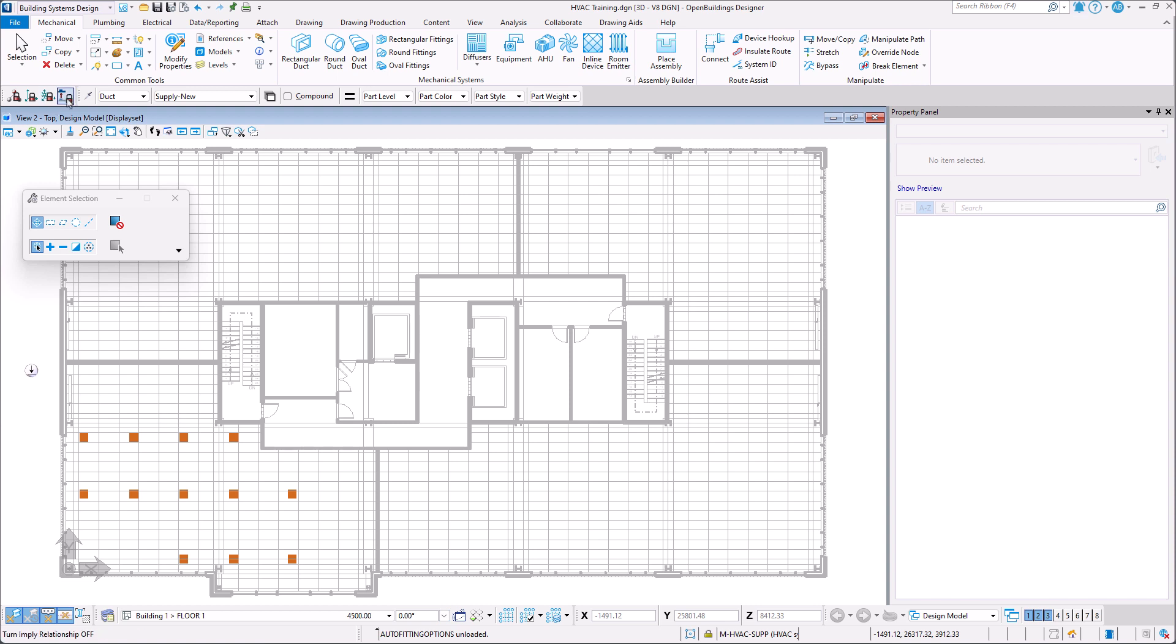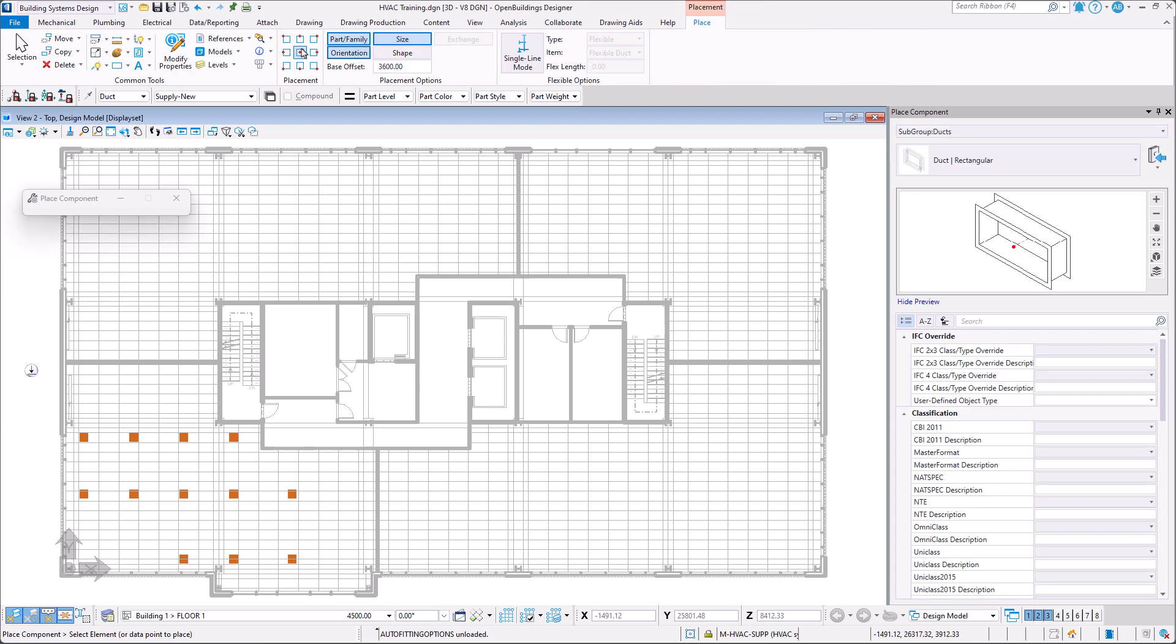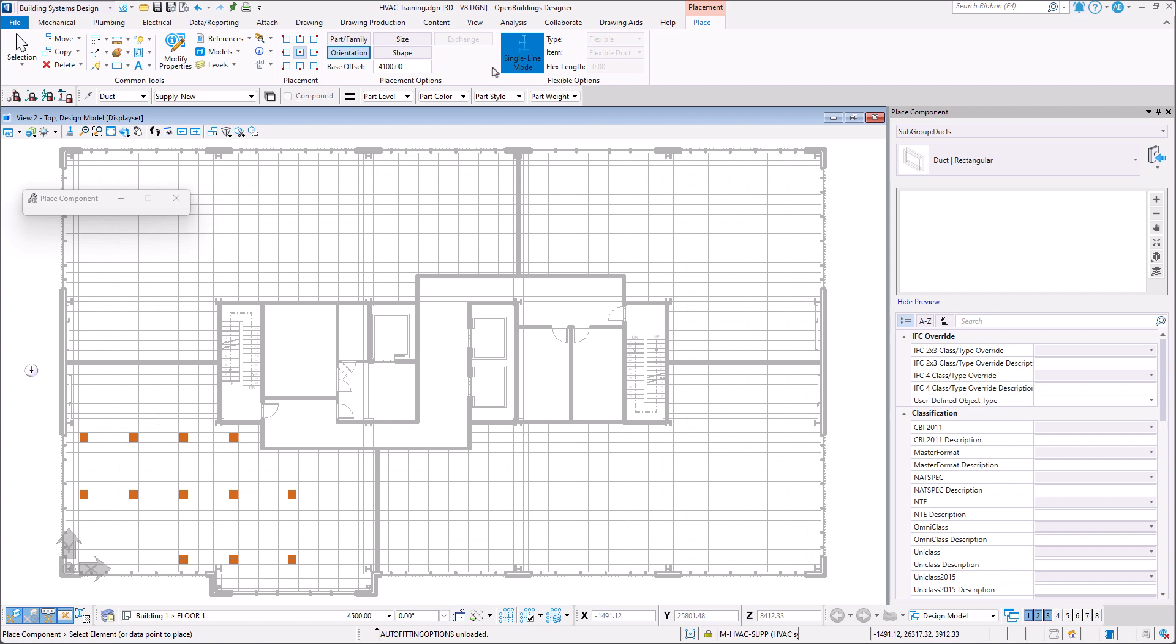Next in the mechanical tab in the ribbon we select the rectangular duct tool. In the placement option section we select a center placement justification, we turn off part and family and size placement options, and set the base offset to 4100 millimeters and enable the single line mode.